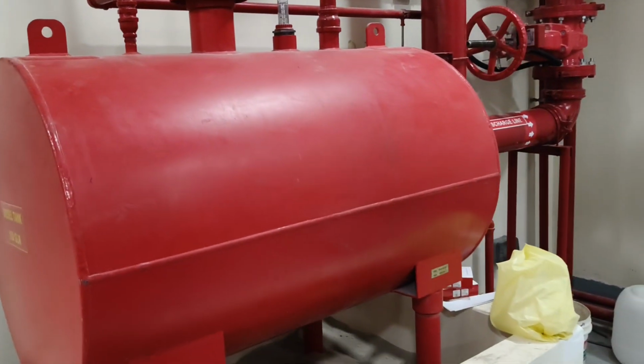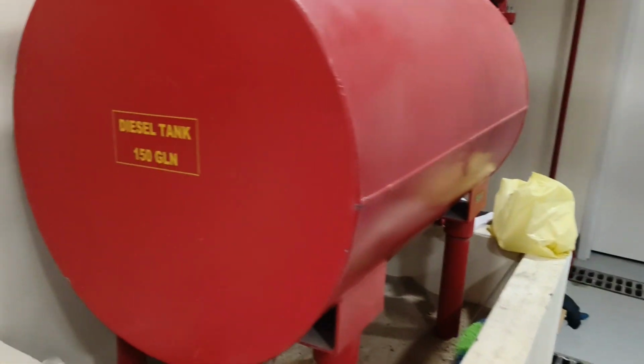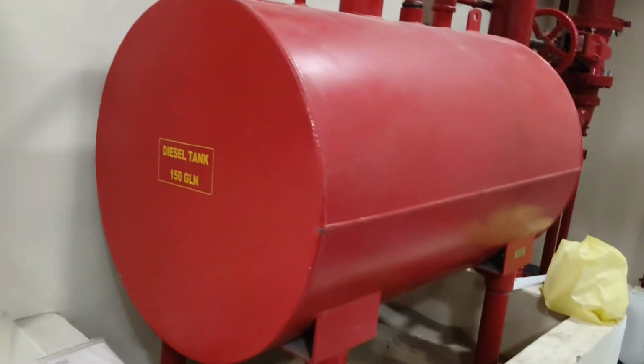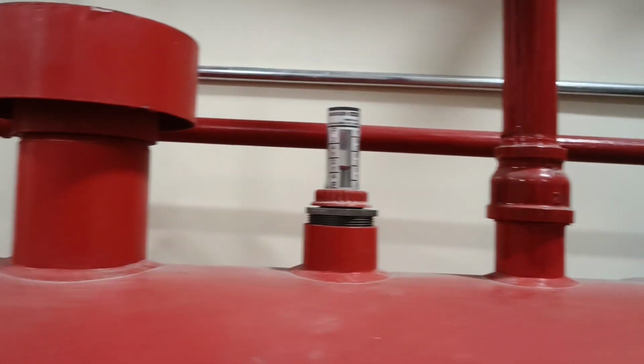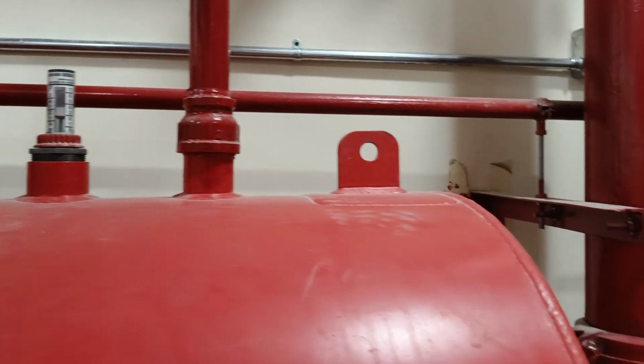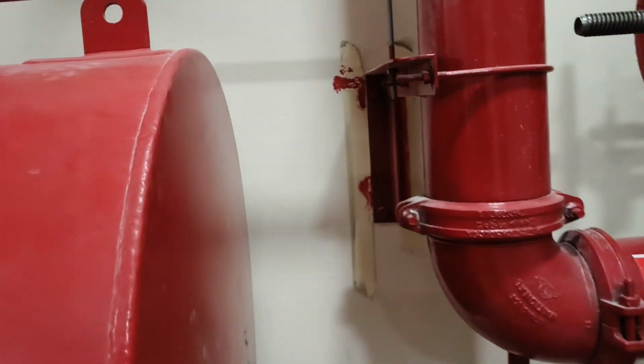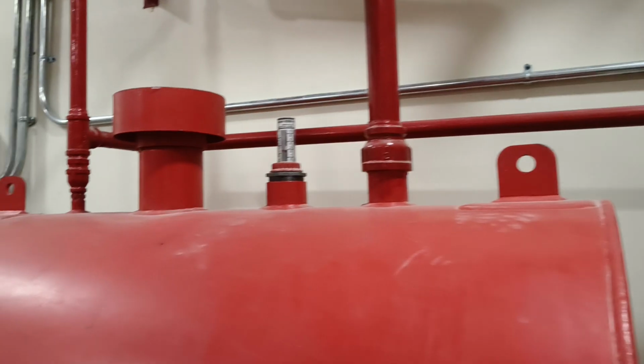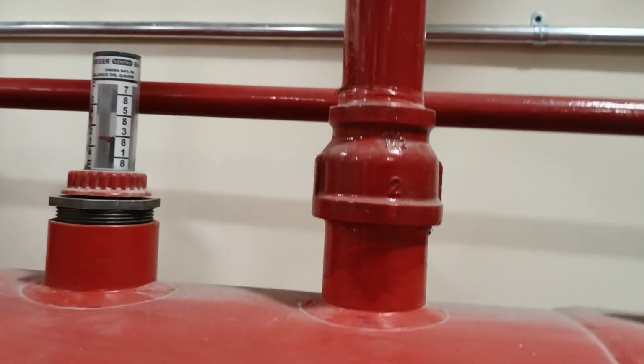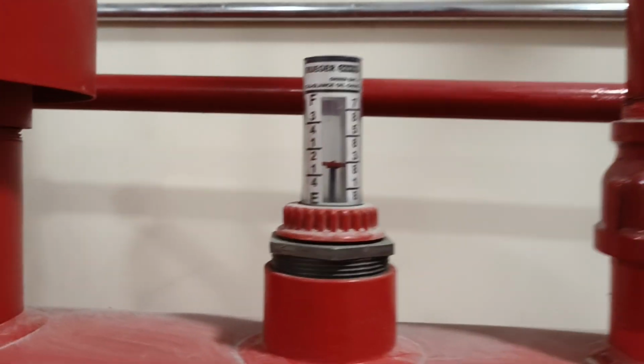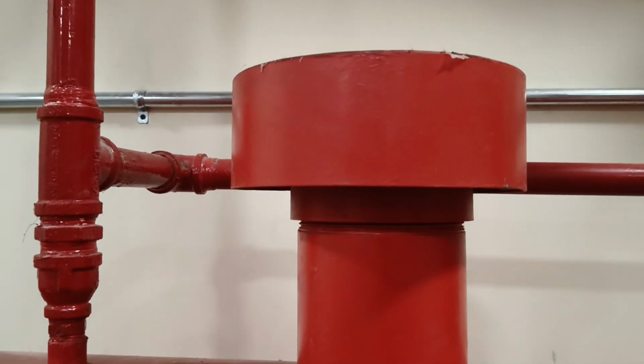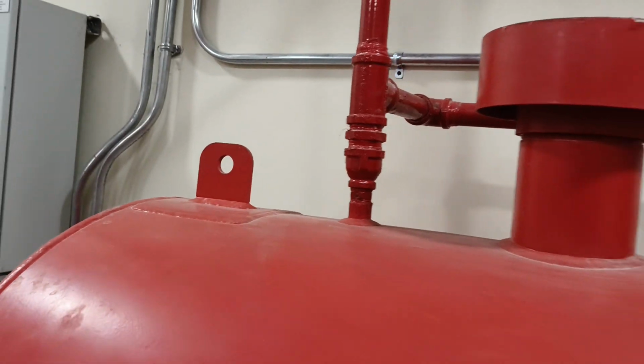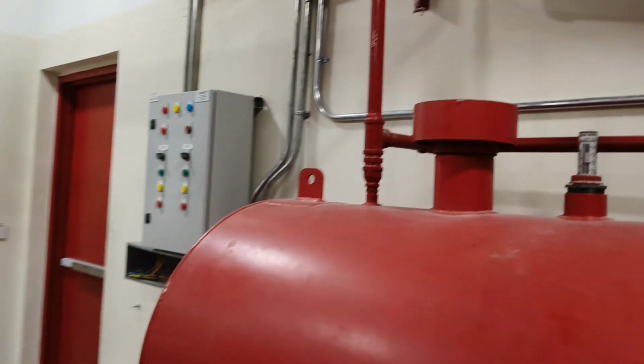And this is actually the diesel tank. It's 150 gallons, okay? And it always comes with the filling line. And this is actually the filling line. This is an air vent. And what we see here is the exhaust also, the exhaust line. So this 2-inch is the filling line, and this is the level indicator. This is the air vent, and that is the exhaust.